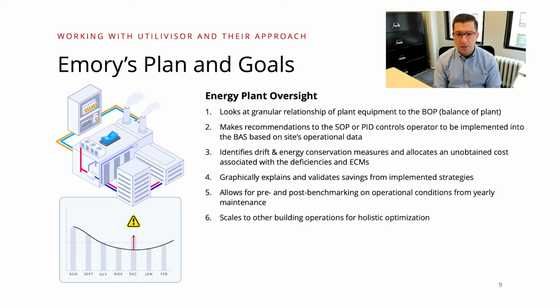We make recommendations, everything from revised reset schedules as it relates to weather. It's a test case scenario where there's engineering theory where everybody knows where certain set points should be, but every plant is a different animal. As the plant gets upgraded with drives, there's a lot more seasonal adjustments you can make, and that can really squeeze out more savings. But you have to worry about whether saving energy at one machine costs too much at another piece of equipment.